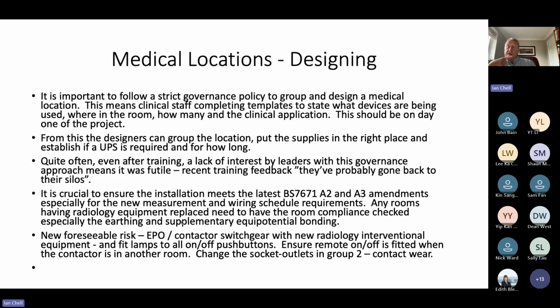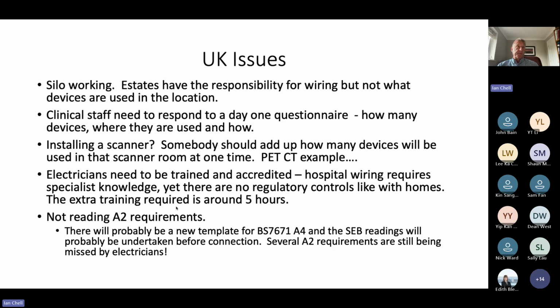Okay. Another issue for designing, which I've seen, and I think I have to be straight, is that managed sites are an issue because of the contractual issues, saving money. You must change all the socket outlets in a group 2. If you're changing the X-ray equipment, simply change all the switchgear and the socket outlets. Because I see worn socket outlets with poor earth connections, and for the medical device, that is important in a group 2. Okay, that's just a quick brief overview.